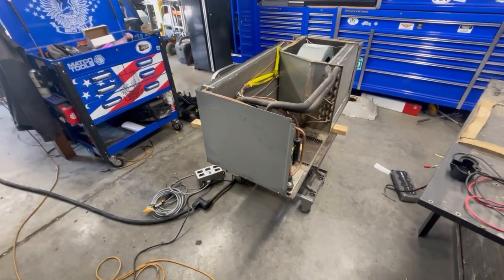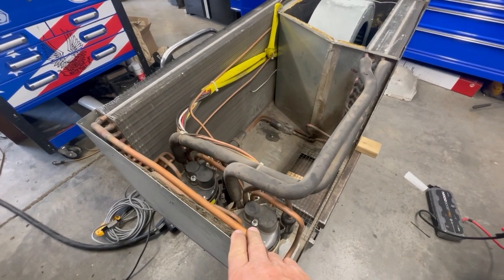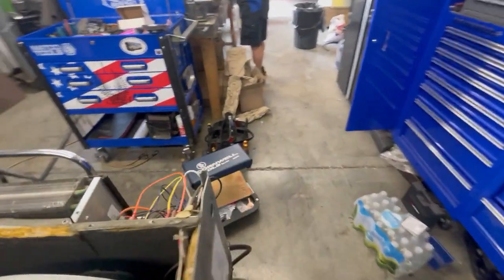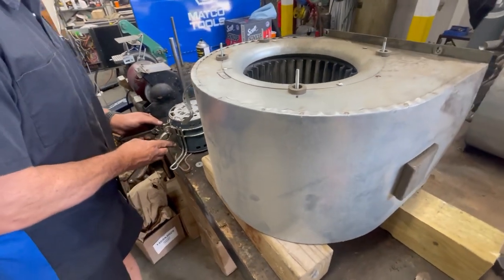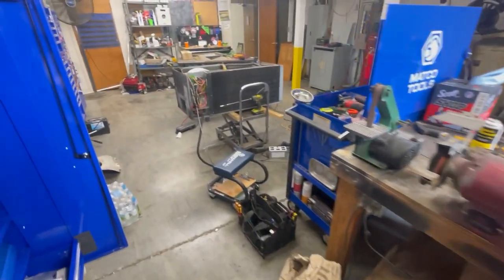So he's going to come back up next week. We're going to, because it's very specific about the size and the length, because that's obviously our metering device. So he's going to be back up here in a couple days and we're going to change it out. So here's the basement air out of this Ultimate Advantage. Now Lewis ran this a couple times on the test bench here and it ran perfect. And the third time we did it, the fan was locked up. So obviously got a problem somewhere in the fan motor assembly. So as you can see, Mr. Lewis is gonna swap that out with a new fan motor, and we updated the capacitor right there. We're gonna change that and update those too, but this will get put back in, should be good to go.